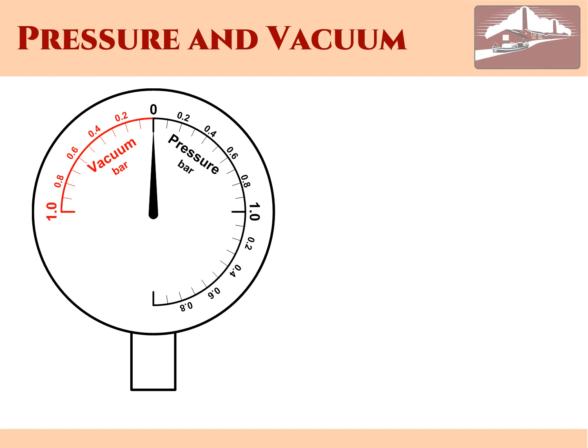So, if we take a new pressure gauge out of its box, it will show 0 pressure, because the pressure inside and outside are the same. This pressure is known as 0 bar gauge, or bar G for short. If we connect the gauge to a sealed vessel and pump air in, the pressure will rise. Conversely, if we pump air out, the pressure will fall, and the gauge will show negative pressure, or vacuum. Now, if our system normally works at very high pressure, this needn't worry us. But if the system works at pressures around atmospheric, all these positive and negative numbers can cause confusion when copying readings.